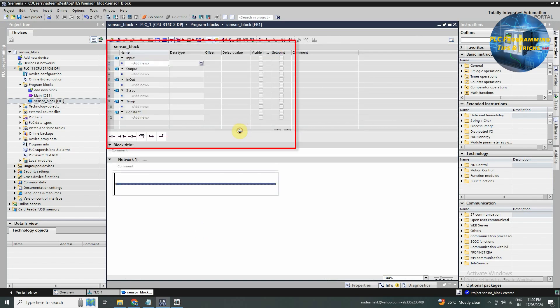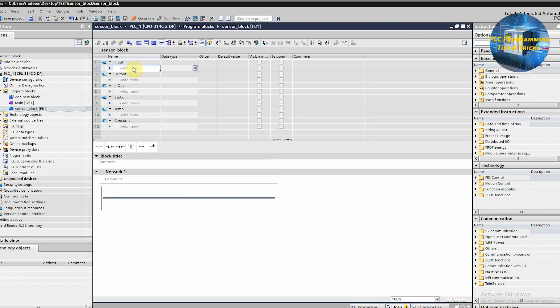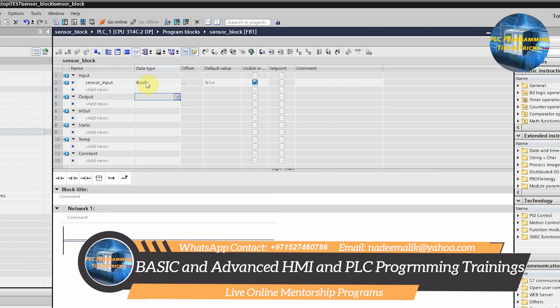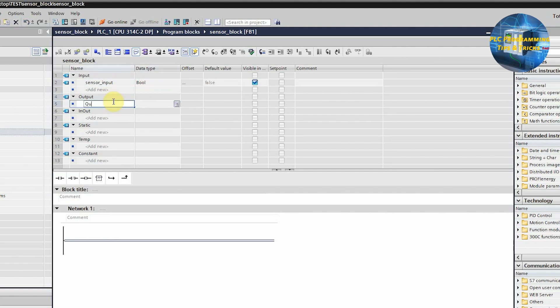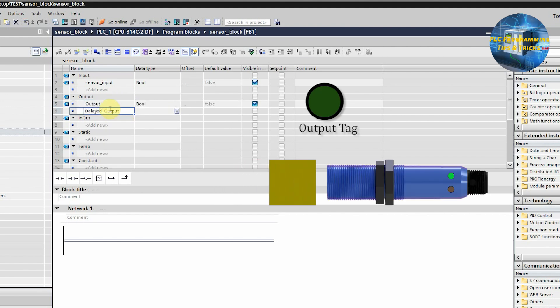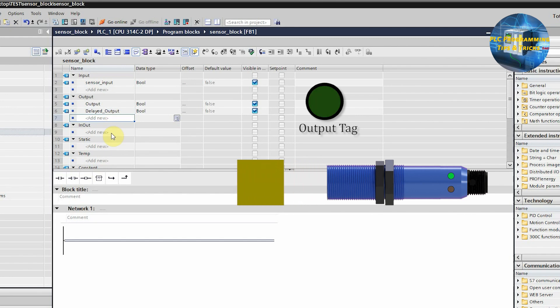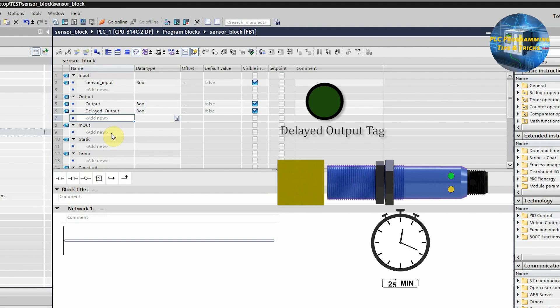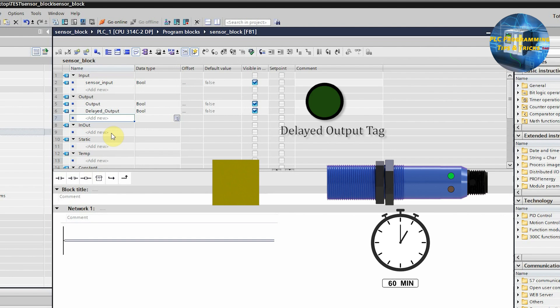Now this function block is created and opened. Next we will click on this down arrow. In this menu we can create tags for this sensor function block. First of all we will create an input tag named as sensor input with boolean data type. Next in the output section we will create two boolean tags: output and delayed output. The output tag will turn on as the sensor input turns on and goes off as the sensor input goes off. The delayed output tag will turn on after some delay as the sensor input turns on and goes off after some delay as the sensor input goes off.